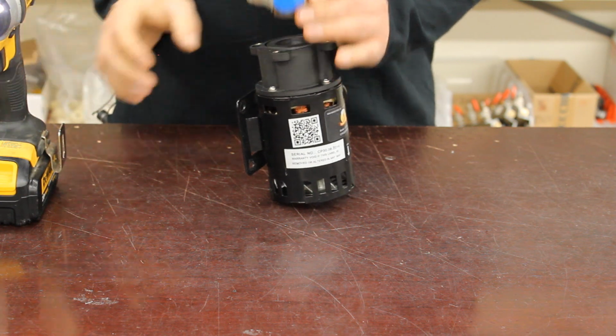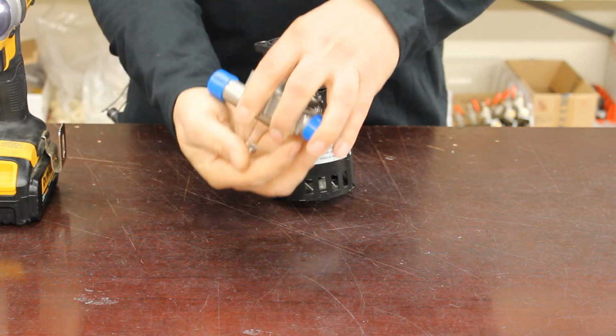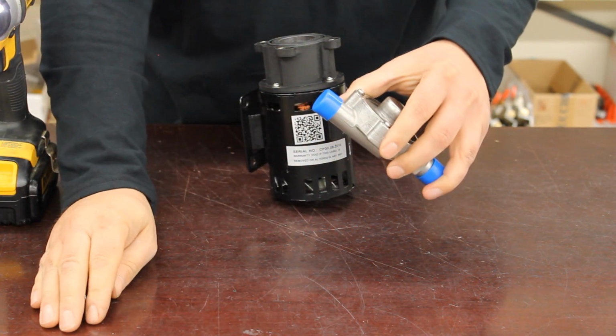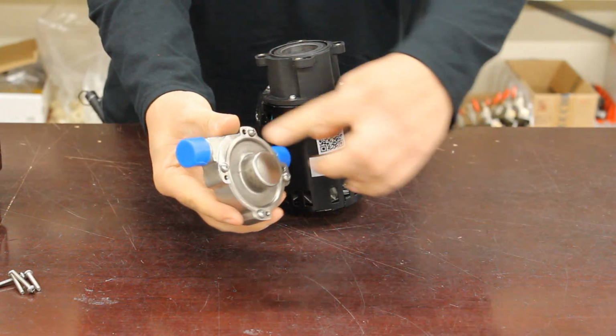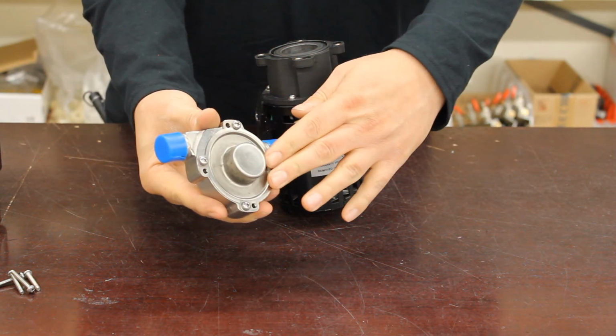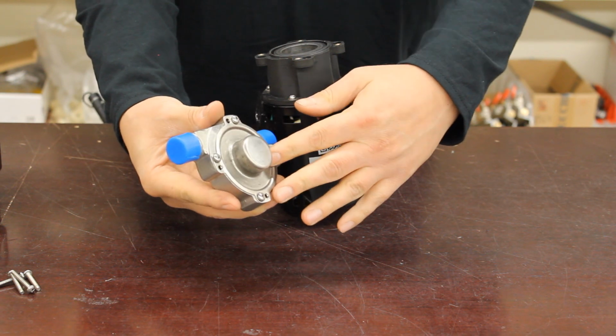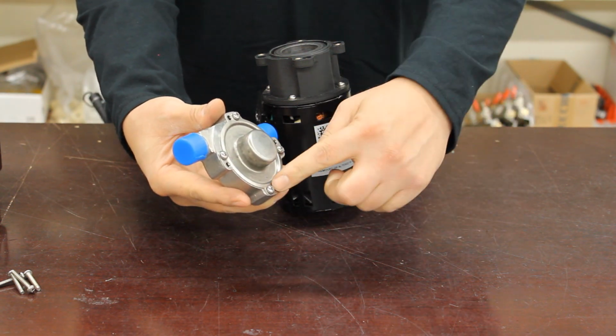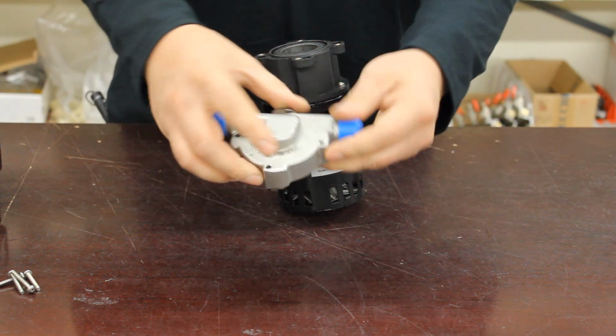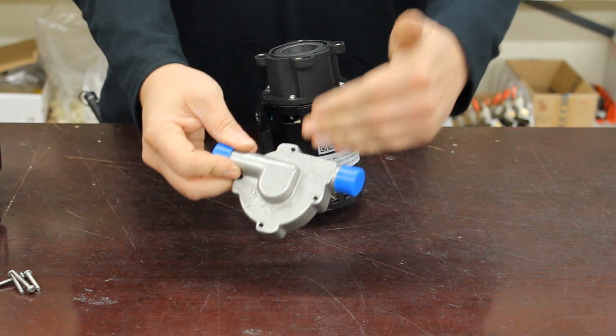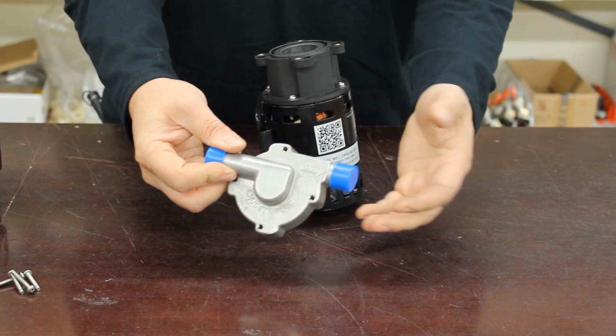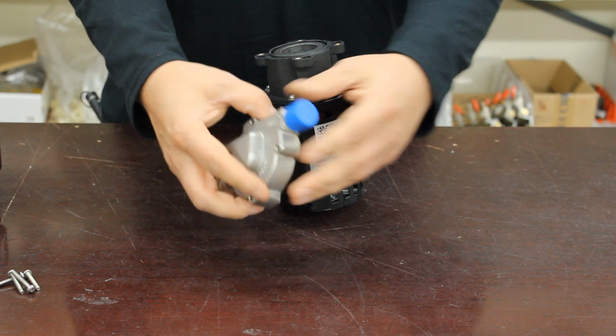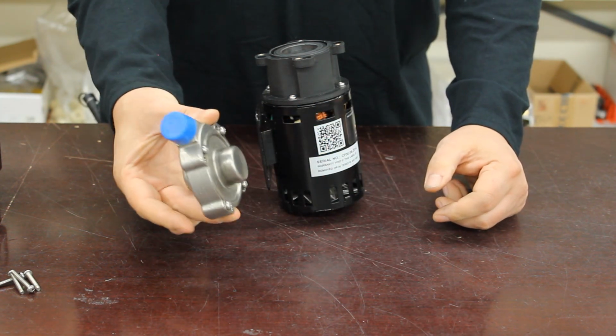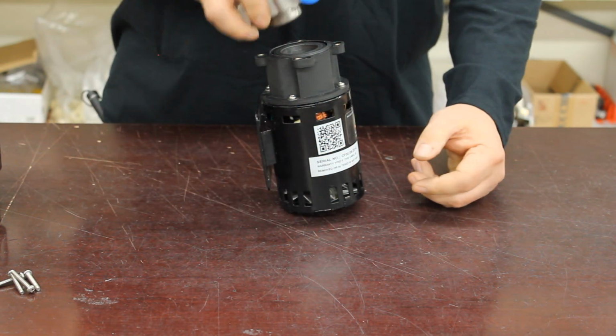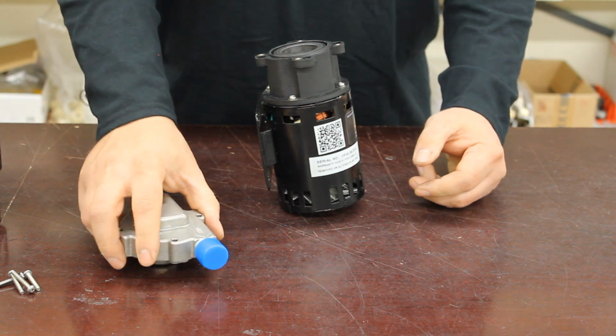Once you do that, the head will come off. Don't lose the screws. So this is the head assembly. You notice that it includes this stainless steel stamped cover plate on the back, which is held on with its own screws. Now this is called the head assembly. So this is the interchangeable piece. If you were to upgrade from a plastic head pump to a stainless, this is the assembly that you would get, and it would just interchange with those 4 screws.